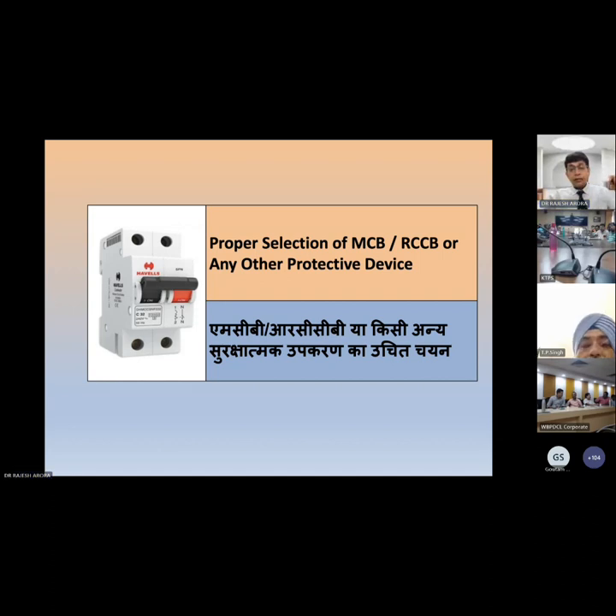In the market, when you purchase your MCB, look at the tripping curve: B type, C type, D type. Look at the tripping curve and the time, and based on that, select your MCB. You select your RCD. It is mandated to use as per the CEA safety regulation. 30 milliamperes we have to use. If you go to the market, 90% of the MCBs available are type C. But you have to choose as per your requirement.